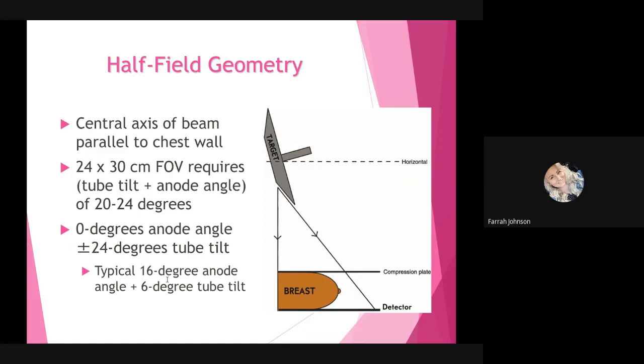So then that brings us to half field geometry. The central axis of the beam is parallel to the chest wall. A 24 by 30 centimeter field of view typically requires a tube tilt and anode angle of anywhere from 20 to 24 degrees. Now, a 0-degree anode tilt would require that the tube be tilted anywhere from positive or negative 24 degrees. Now, the typical 16-degree anode angle is accompanied by a 6-degree tube tilt. And what this means is that because your chest wall runs parallel to the central axis of this beam, we have to tilt our anode so that we can utilize the high energy photons on the cathode side, because this is the denser part of the breast tissue against the chest wall.